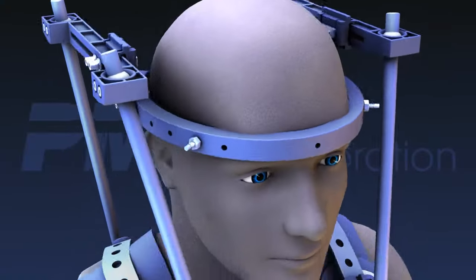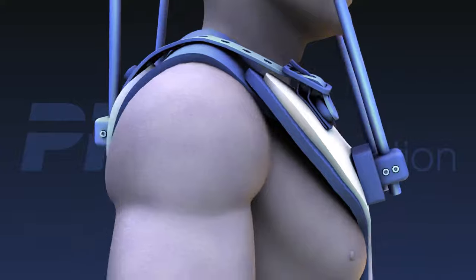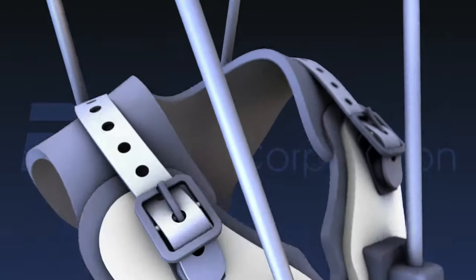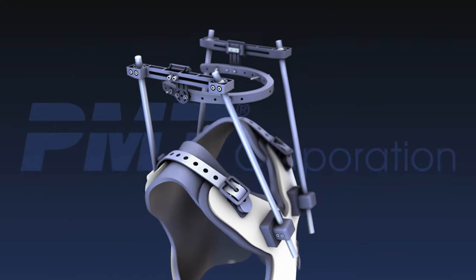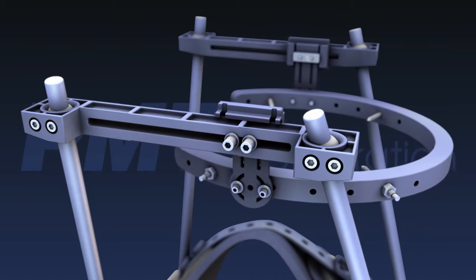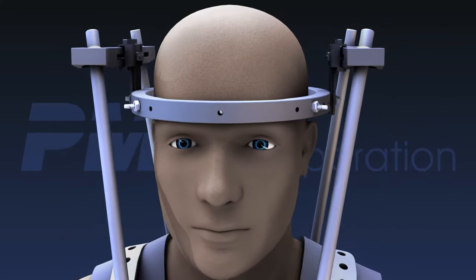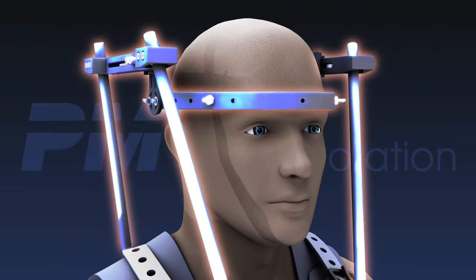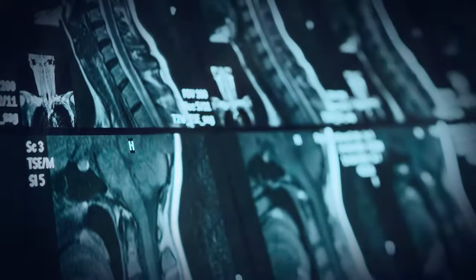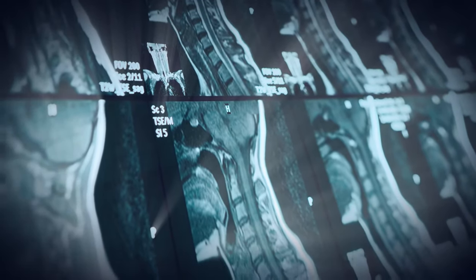Before beginning this presentation, several design features of the PMT HALO deserve special attention. First, nylon ball joints are used to connect the HALO rods to the ring and vest. These joints are designed to allow maximum adjustability and facilitate accurate and rapid cervical spine positioning. Secondly, the PMT HALO is constructed of lightweight graphite and titanium, rendering the device CT and MRI conditional. Recent studies have documented that this combination produces the clearest MRI images.